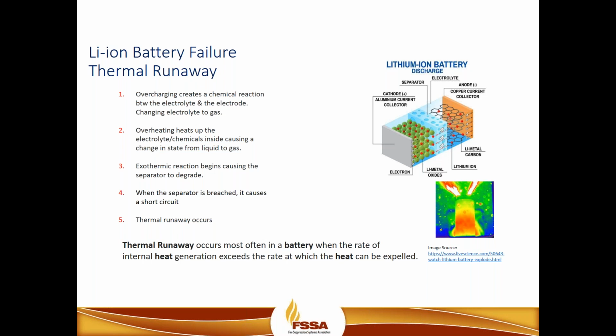allowing for the internal pressure and the separator to break down. So really where you have complete thermal runaway that occurs is once that separator that we talked about right here in the middle, in between separating the anode side and the cathode side, once that separator breaks down is really when the liquids begin to mix and they change state to a gas, and that off gas pressure occurs. And so once that off gas occurs is really the critical time at which we want to achieve some form of early warning detection. This is, you'll see in a few slides, we'll talk about that critical time. The South Koreans kind of coined that term as the golden time, and we'll touch on the golden time more during the presentation. But of course, once you achieve thermal runaway, it cannot be stopped.